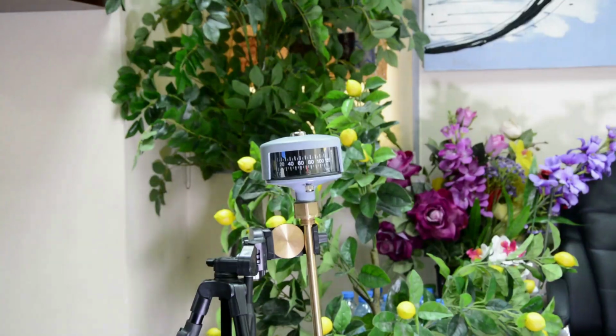Another very important aid in continuous monitoring of the status of the transformer is the oil temperature. By continuously monitoring this temperature, we can have a feedback about the condition of the distribution transformer. Because during abnormal condition, overload, short circuit will generate heat, which will increase the temperature of the oil inside the distribution transformer. So monitoring the temperature of the transformer is crucial. And this temperature is monitored using a thermometer. And the most popular type is the bimetal one.